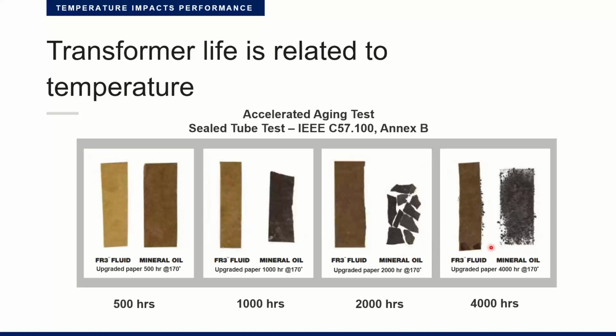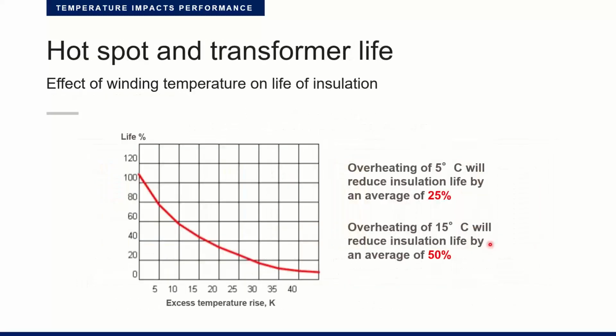So actually it's not the load of the transformer which reduces the lifetime. It's the corresponding temperature which has a direct impact on the insulation. So if you could go to the next slide, please. Here you see a graph. I mean, the weakest point in the whole insulation chain is the hotspot. So this is why we talk that often about the hotspot. And this curve shows the hotspot temperature, and it says overheating of 5 degrees Celsius will reduce insulation life by an average of 25%. And overheating of 15 degrees Celsius will reduce insulation life by an average of already 50%.